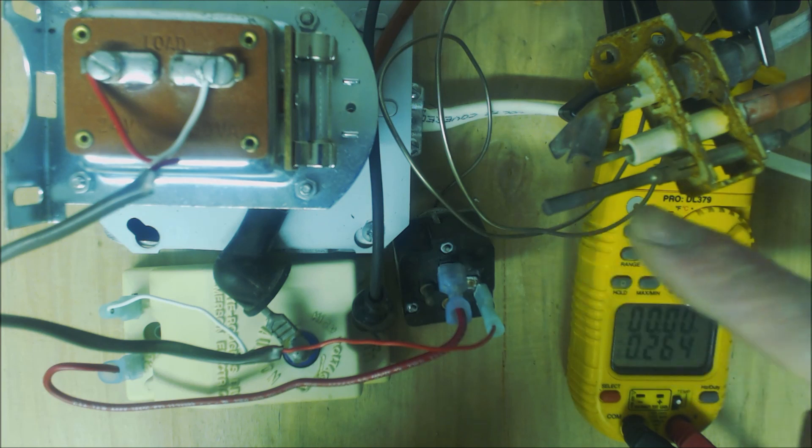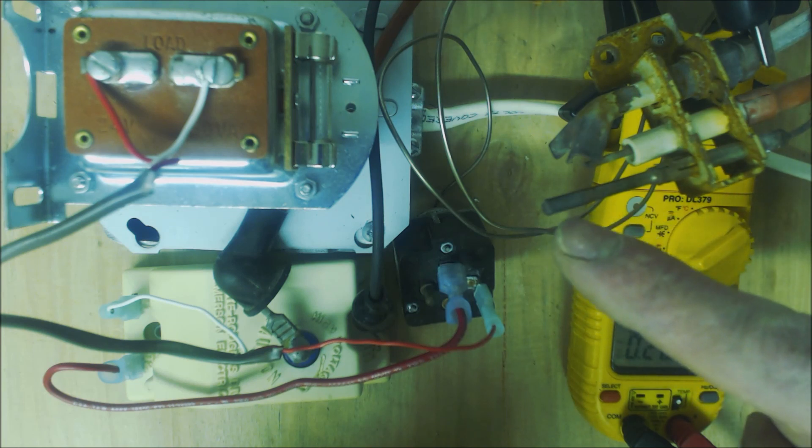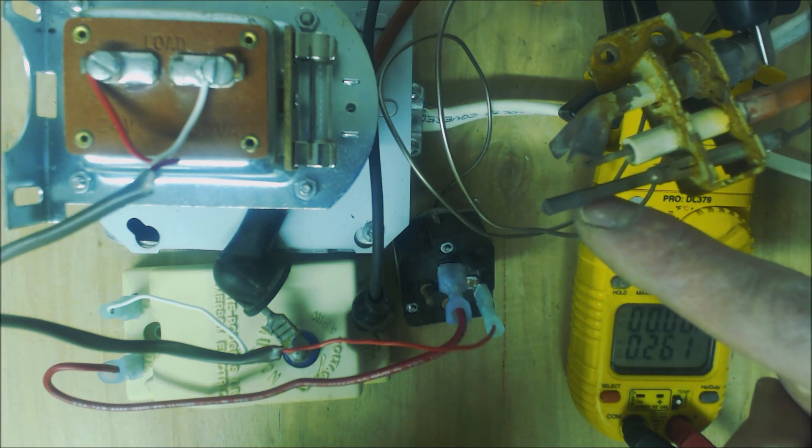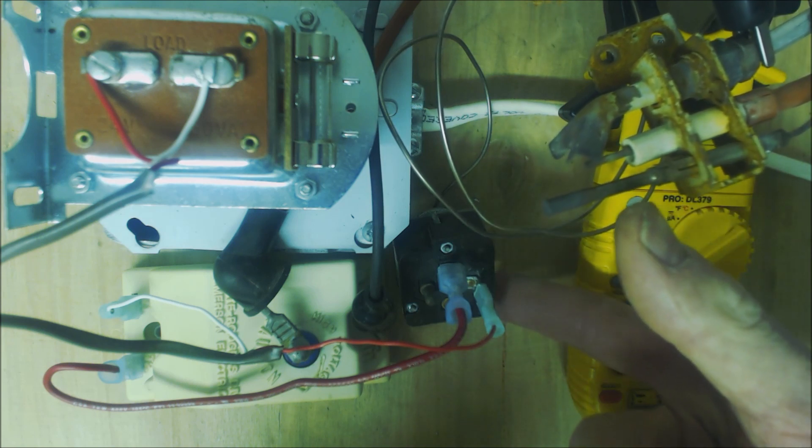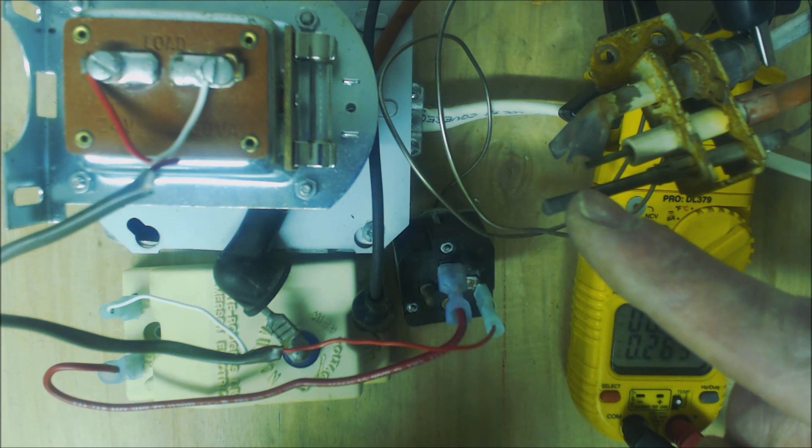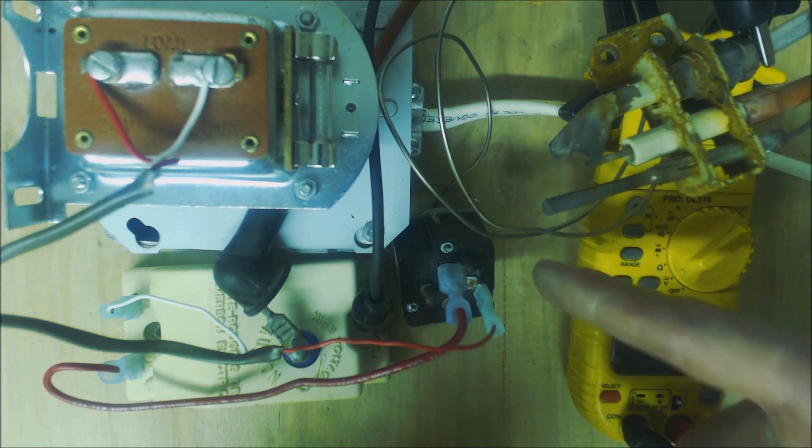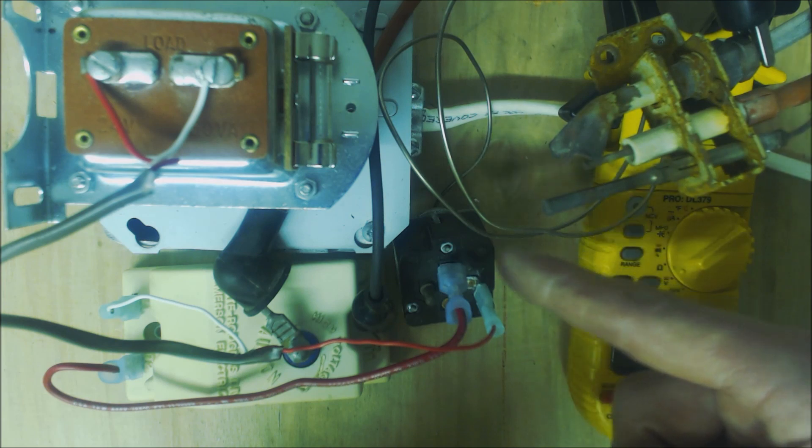This is not a thermocouple and not a flame sensor - this is actually a mercury flame sensor. When this heats up, it sends mercury through this tube over to a diaphragm in the relay, opening and closing contacts.